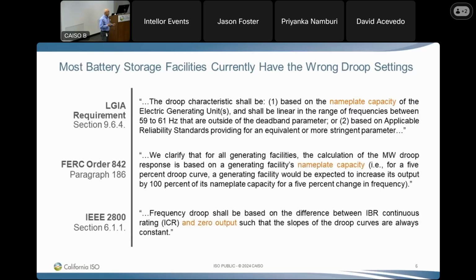But what's a bit of a controversy is that a lot of the units in California have the droop set based on IEEE 2800. If you look at IEEE 2800, it says the droop setting should be based on a range from 0 to essentially what ICR is equivalent to your Pmax.